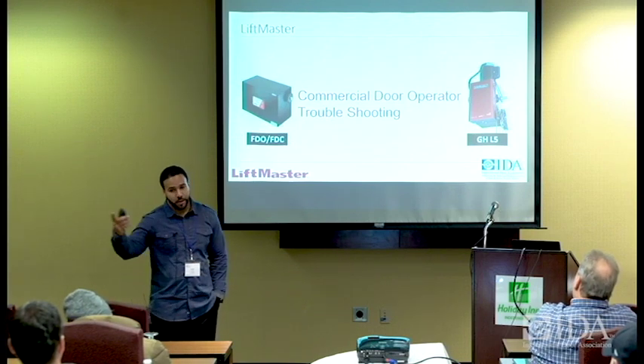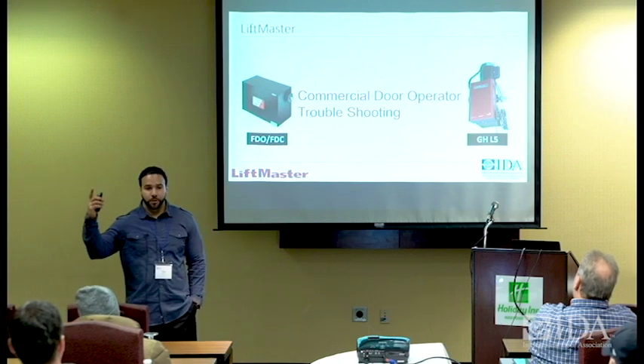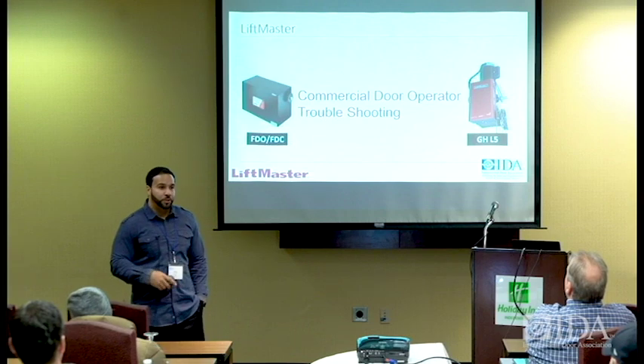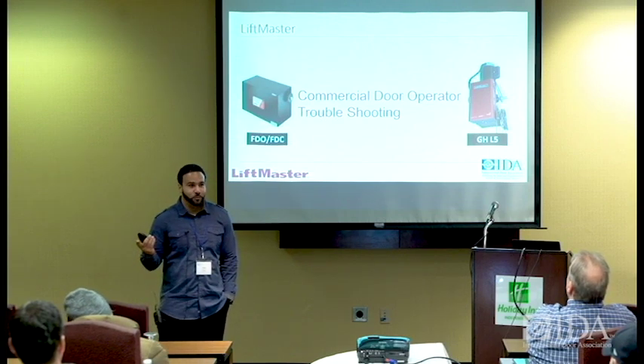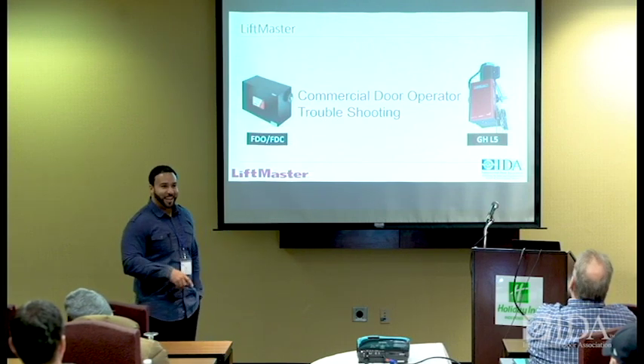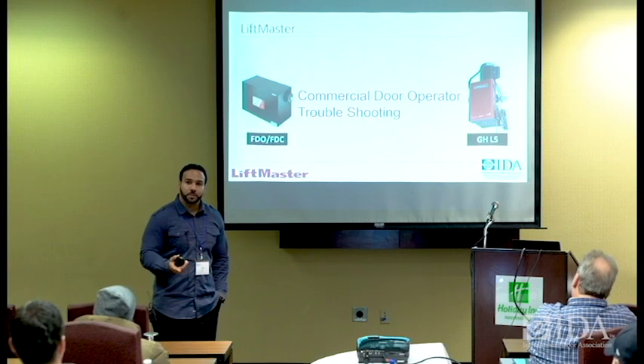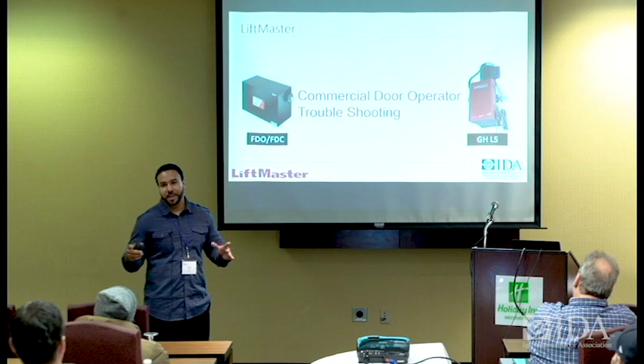And then they also had a situation where you had the breaker or the main power supply 350 feet away. Then you want to use tight, 22 gauge wire? What do you think is going to happen? Okay, it ain't never going to make it. So that's one of the things that you'll see in those types of situations where it's a really big outfit that has over 150 doors.